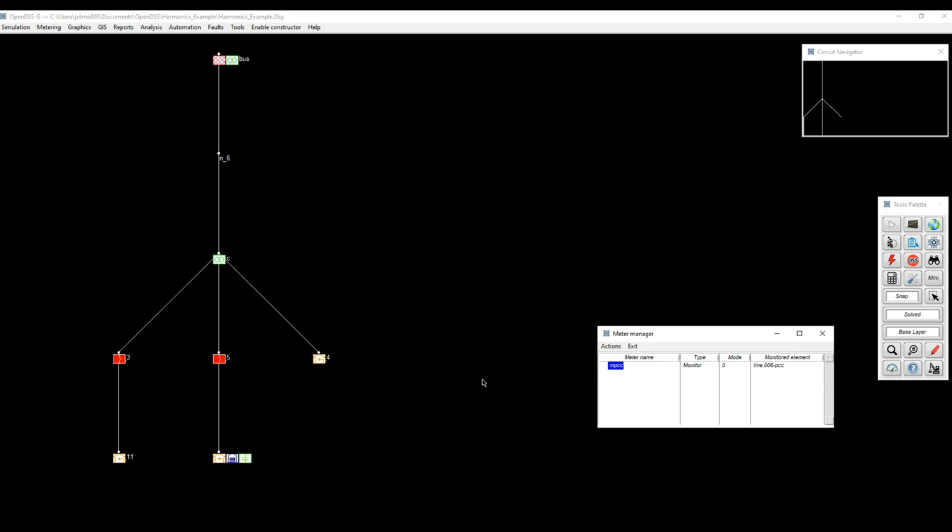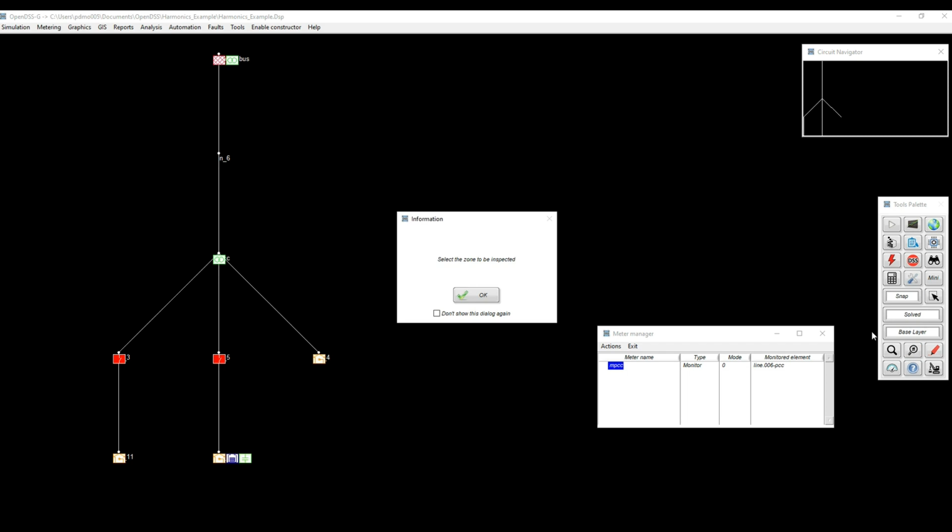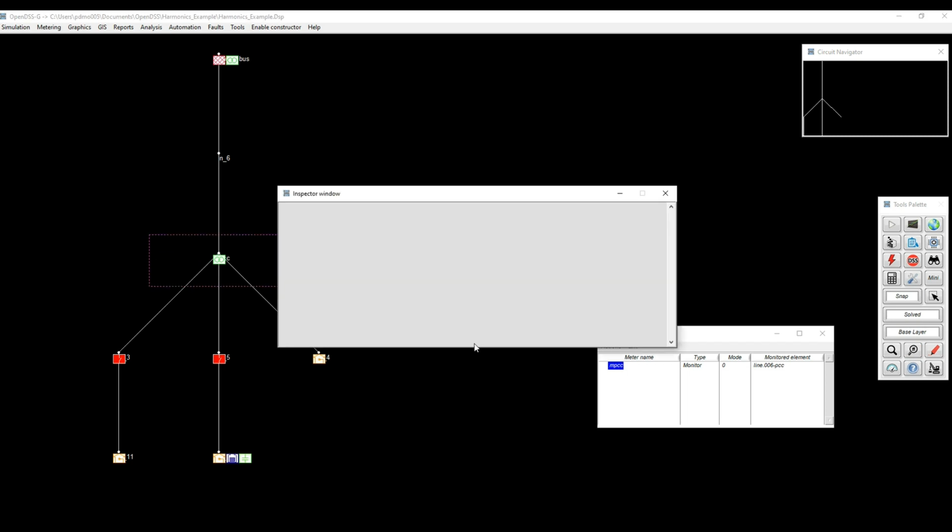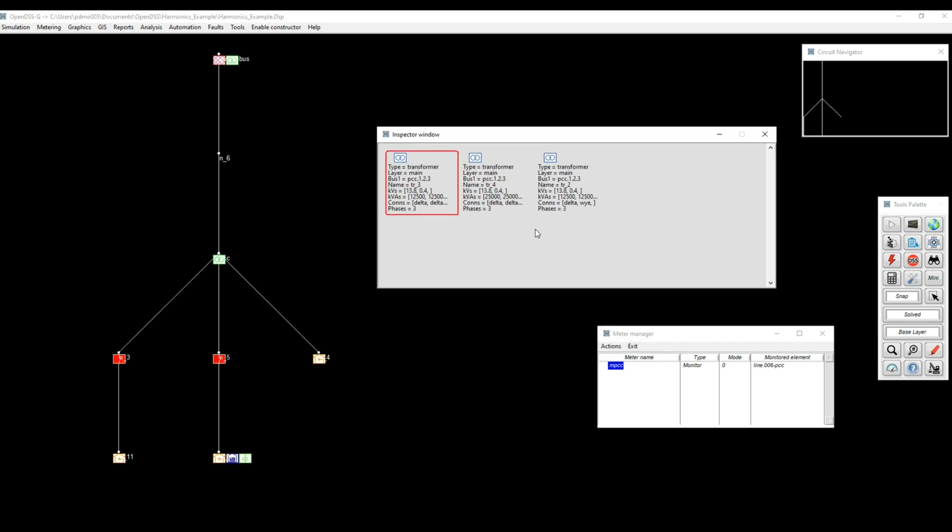Also talking about the transformers that we have in the system, the ones that are connected at the point of common coupling to the loads, we can see using the explorer that those transformers have different configurations. So just by using the explorer, you can look that the configurations could be delta, delta, delta, delta, delta, Y. This is for shifting the phase angle of the current for each one of the loads, which is basically the effect that the IEEE 519 is proposing in this example.